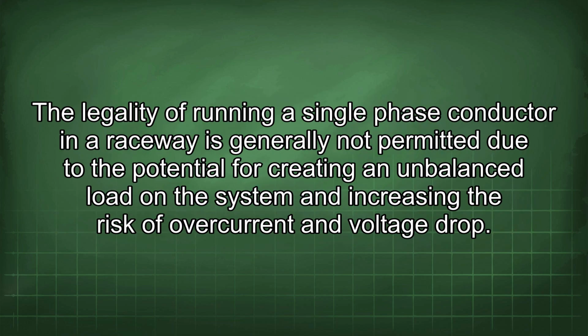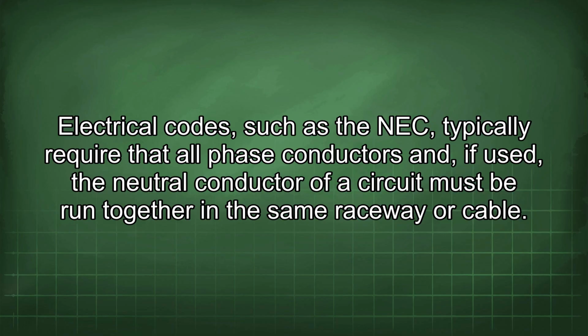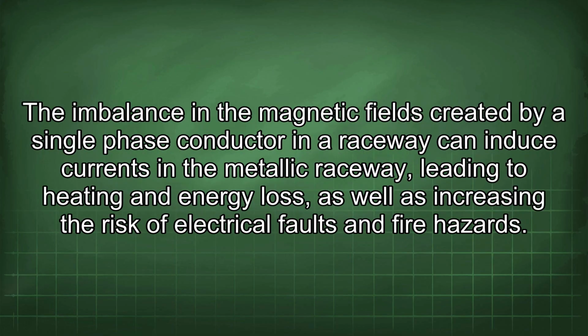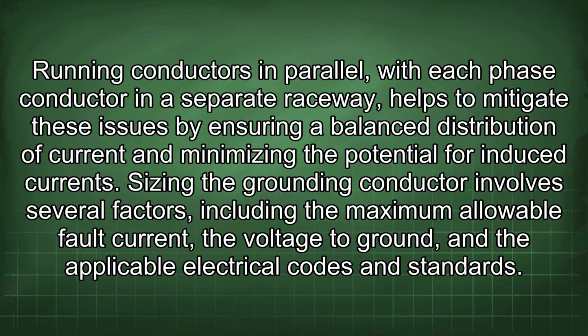The legality of running a single-phase conductor in a raceway is generally not permitted due to the potential for creating an unbalanced load on the system and increasing the risk of overcurrent and voltage drop. Electrical codes, such as the NEC, typically require that all phase conductors and, if used, the neutral conductor of a circuit must be run together in the same raceway or cable. The imbalance in the magnetic fields created by a single-phase conductor in a raceway can induce currents in the metallic raceway, leading to heating and energy loss, as well as increasing the risk of electrical faults and fire hazards. Running conductors in parallel with each phase conductor in a separate raceway helps to mitigate these issues by ensuring a balanced distribution of current and minimizing the potential for induced current.